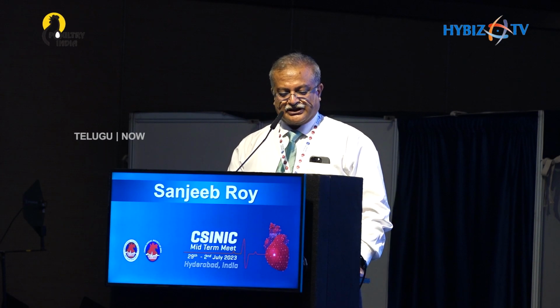The use of laser follows the principle of 5S, where we need to select our patients. We need to size the catheter, which should be less than 2/3 of the vessel diameter. We need to adjust the settings, which we call fluence and frequency. Fluence is the pressure with which you are hammering, and frequency is how frequently you are delivering these energies. Then, most importantly, we need to use a saline flush and keep the system clear of contrast, because contrast can result in high pressure energy delivery. And very importantly, we should advance the catheter very slowly.